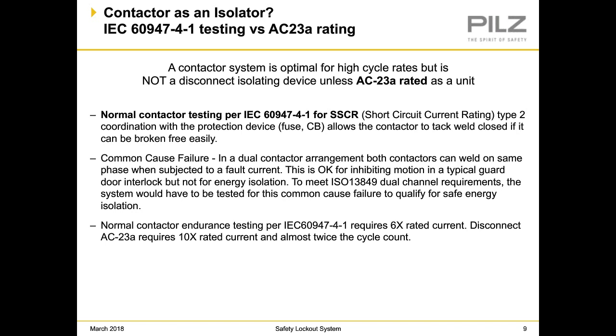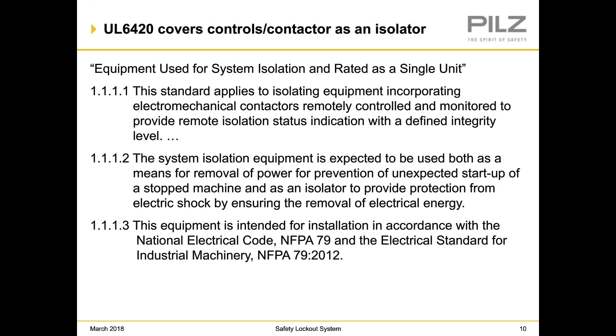Having mentioned that, there's a standard, UL 6420, that covers controls and contactors as an isolator. The standard applies to isolating equipment incorporating electromechanical contactors, remotely controlled and monitored to provide remote isolation status indication with a defined integrity level. System isolation equipment is used both as a means for removal of power for the prevention of unexpected startup of a machine, of a stop machine, as well as an isolator to provide protection from electric shock by ensuring the removal of electrical energy, such as lockout tagout.